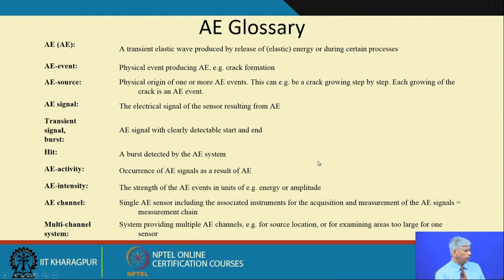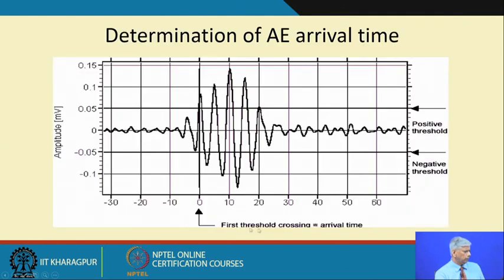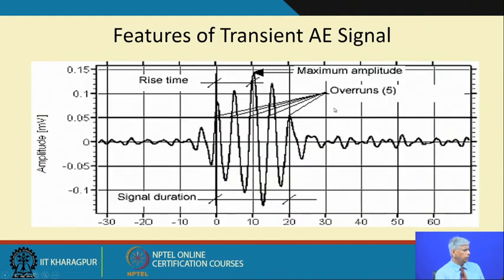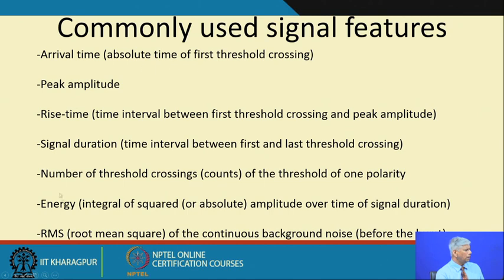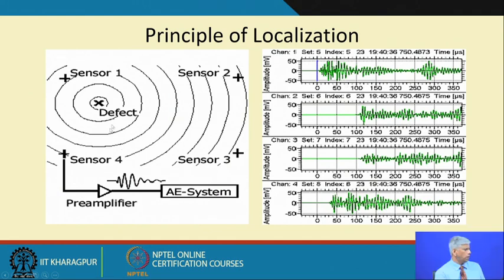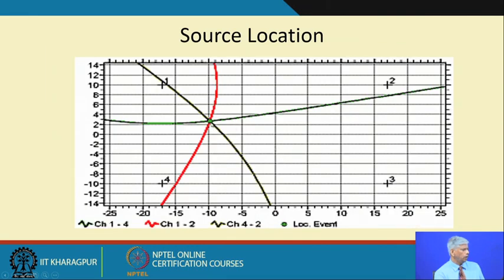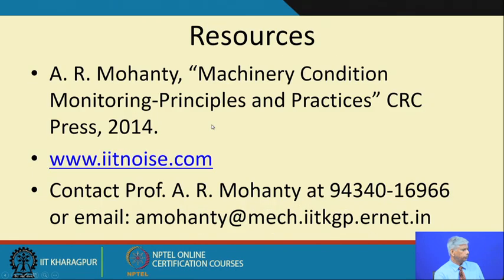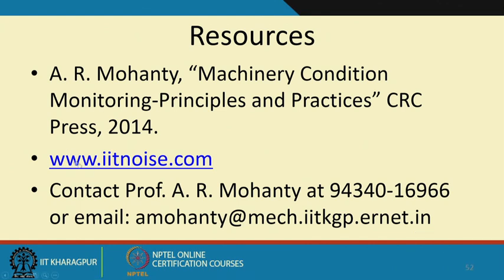The features of a transient AE signal include rise time, maximum amplitude, number of overshoots, and arrival time at a particular sensor location. These features allow quantification of the signal to give clues about the condition of the machine or component. Calibration is done using a pencil lead break test, and through Time Difference of Arrival (TDOA) — where different sensors record different arrival times — a triangulation technique can locate the fault source. More details can be found at iitnoise.com.